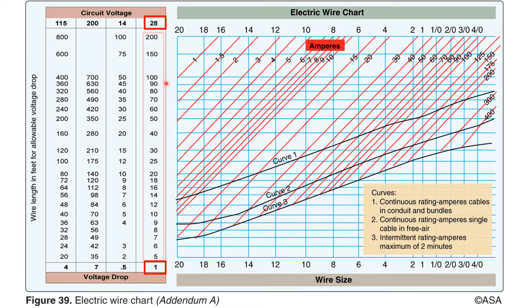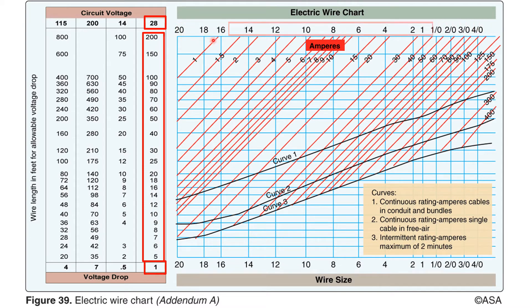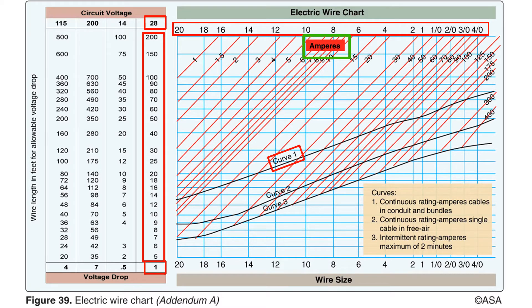The numbers running vertically in this column are for wire length in feet. The numbers across the top of this chart are wire gauges, with the larger numbers representing the smaller gauges. The red diagonal lines represent current flows in amperes. Curve 1 represents wires that are run in a bundle with other wires or through a conduit. Because the heat generated by wires run in bundles or conduit cannot dissipate as readily, a heavier gauge wire is often required. Curve 2 represents wires that are run singly in free air, which dissipate heat more readily, so a smaller gauge wire can oftentimes be utilized.